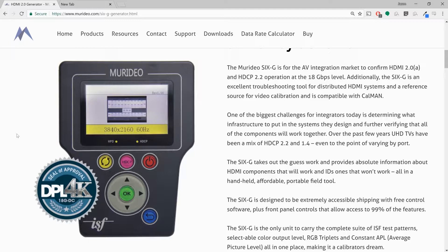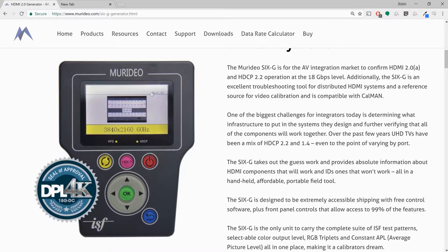Once you've got it plugged in, go ahead and power the Murideo generator up and find out which revision number you have on the generator currently. So once the generator is powered up, take a look in the upper right hand corner and as you can see in this example it's revision 1.0. That becomes very important when we go to download the firmware for this machine.